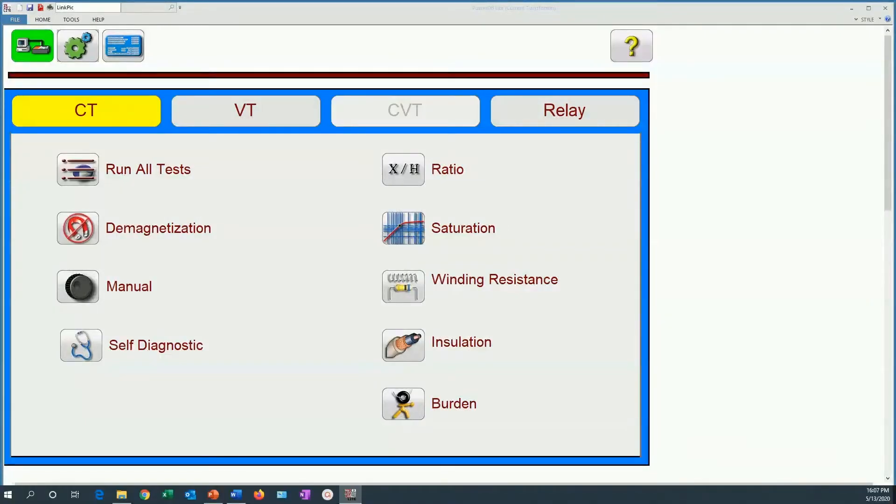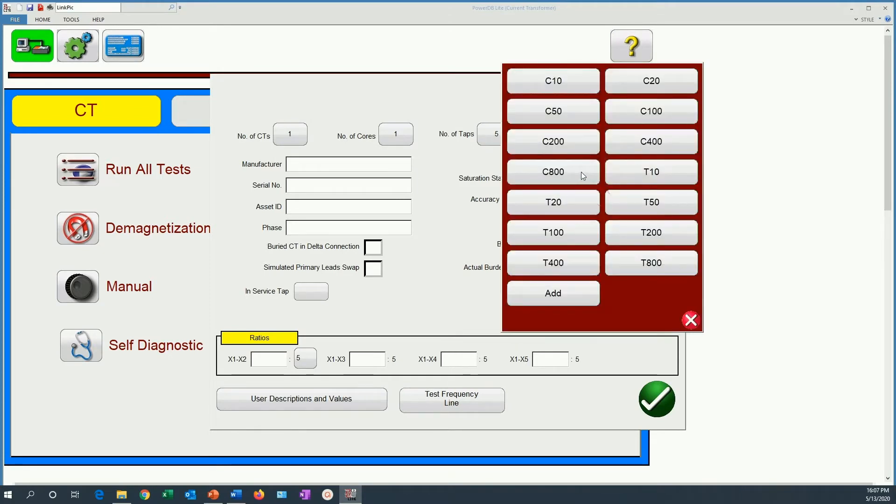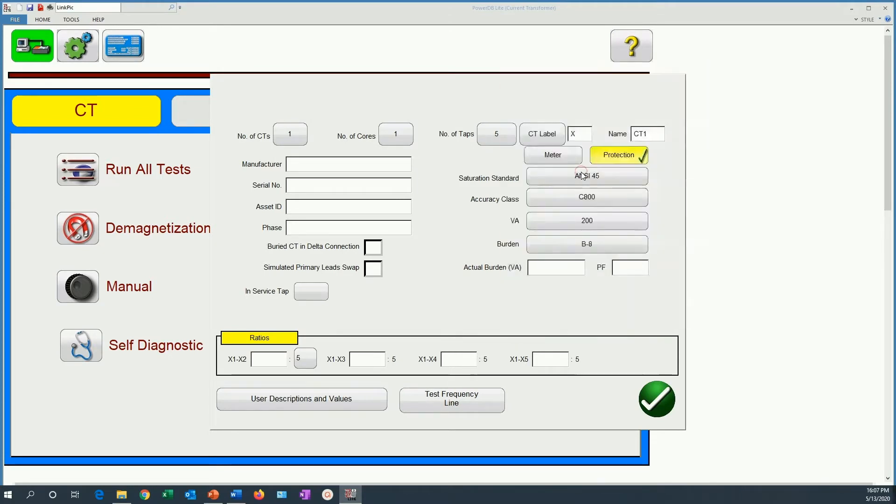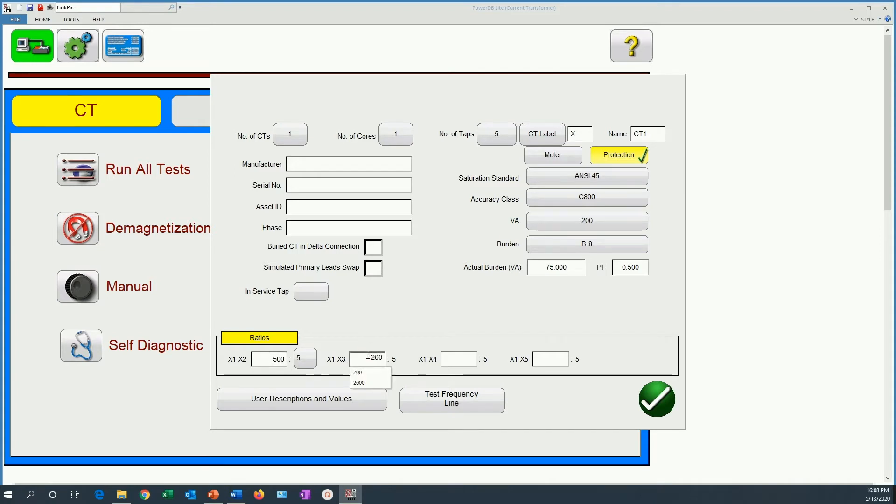In order to test the burden using the MRCT, the first thing we usually do is go to nameplate and enter the nameplate information of the CT. In this case let's say it's a C800 CT with an actual burden of 75 VA at a power factor of 0.5. Here we don't really need to fill all the ratios but as part of a proper testing procedure you would do that. So let's do it for this CT as well.